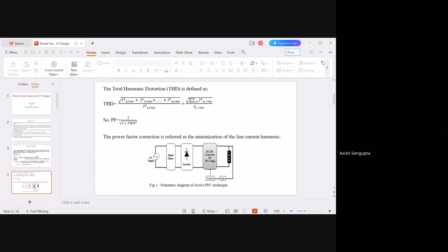That is, keeping the harmonic content to a minimum level. The effect of harmonics and its problems on power systems is observed as significant, and hence electricity regulatory commissions and utilities all over the world are penalizing users for harmonic dumping into the supply lines. And the Central Electricity Regulatory Commission of India has given a guideline to institute the IEEE standard 519-1992 on permissible limits for harmonics in electrical systems, and both the utility and users should understand the standard and the essential time and specified limits.